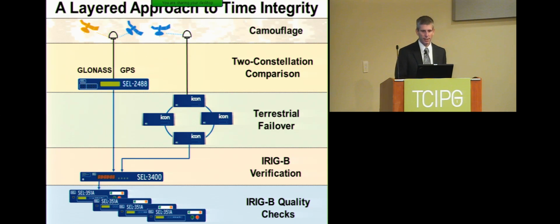Another way is to use terrestrial time distribution, over systems like SONET or TDM, to distribute precise time over a wide geographical area and compare it against a local source. In this case, I have the 2488 and the Icon system plugged into a 3400, and that 3400 is what we call an IRIG-B verification system. It compares the two time streams, and if they disagree, it can throw an alarm.